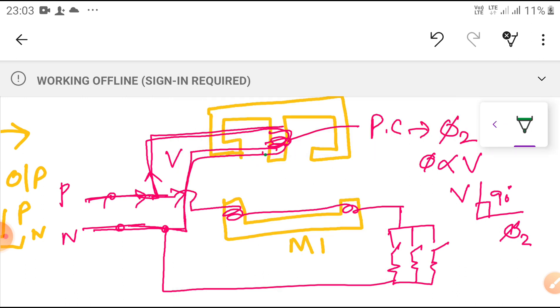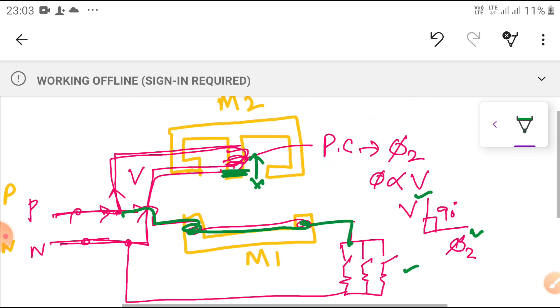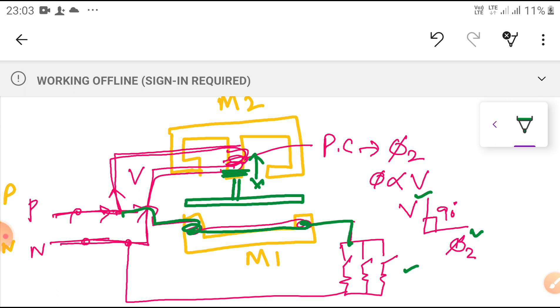We provide one shading ring and by adjusting its movement on the upper and lower side, we make the displacement between the voltage and the produced flux exactly 90 degrees. Now coming to the lower side — suppose all loads are opened. Then the current circuit is open, no current is flowing, so no flux is produced in M1. The phi 2 from the voltage coil links with the aluminum disc, but M1 flux is zero because no current flows through the current coil. Therefore, there is no rotation of the disc and no recording of values.